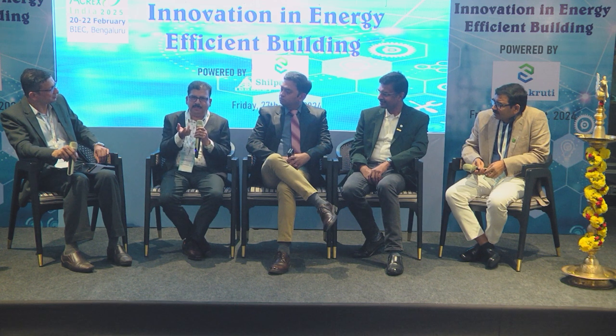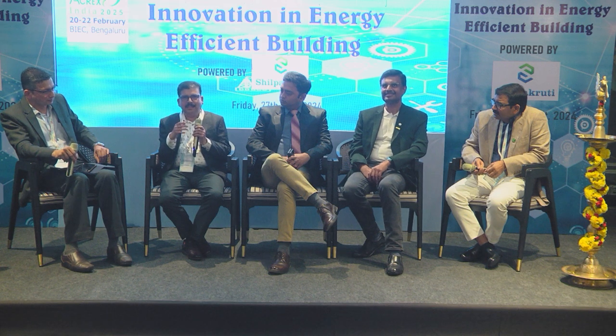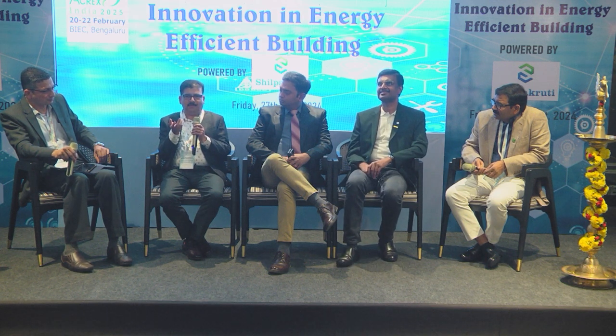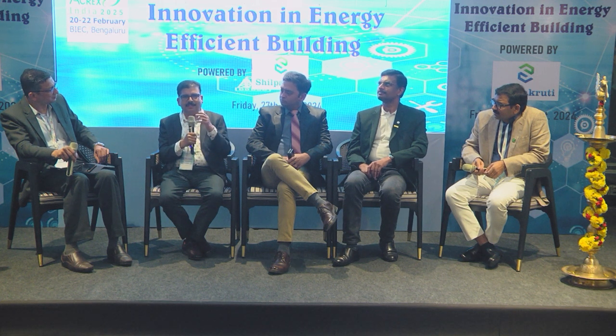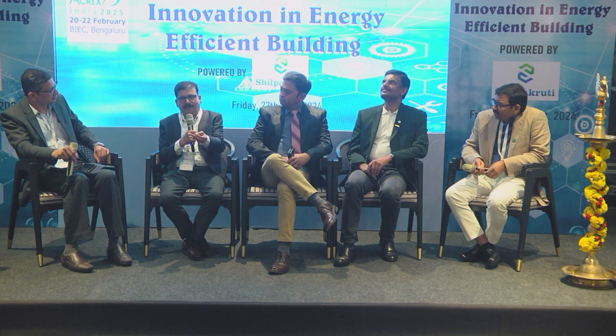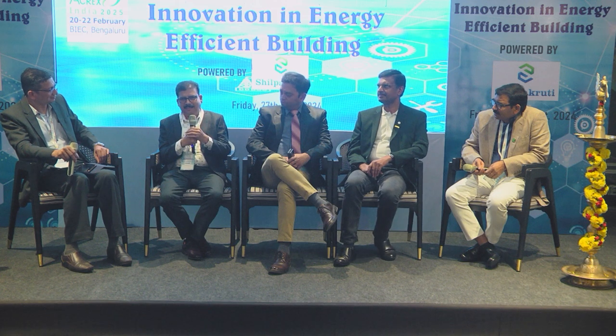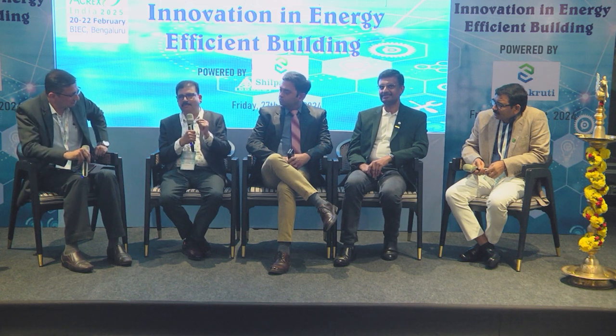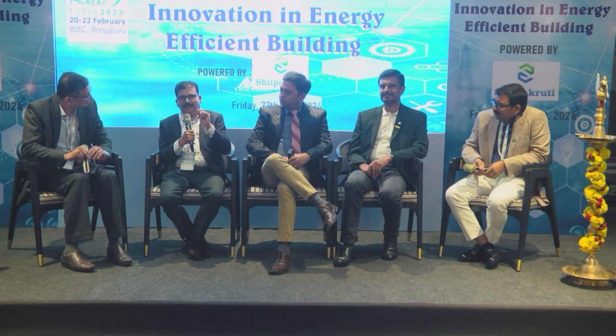When selecting a PIBCV, people select based on flow rate and pipe size. Nobody goes into deep selection of KVS value or valve authority. If you don't select proper valve authority, it will not modulate properly. Whatever the intent of spending money on that energy efficient valve or PIBCV, you will not get it because you are selecting the wrong valve. So the first and most critical thing is the design, how you select each and every item.